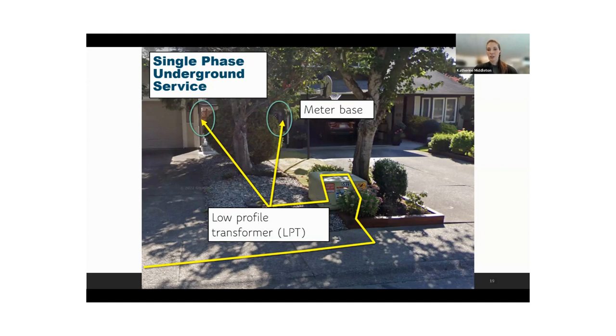So a key consideration to planning a subdivision, or putting 4 to 6 units on a single family dwelling lot for example, is that we need to make sure adequate capacity and physical space is built in and considered. Every piece of equipment on our distribution system has a place and a location. It's not possible to have a transformer placed some distance away feeding multiple houses, as we need to consider our voltage drop, the size of the transformer that we have, and delivering usable voltage or power to the customer as dictated by national standards.